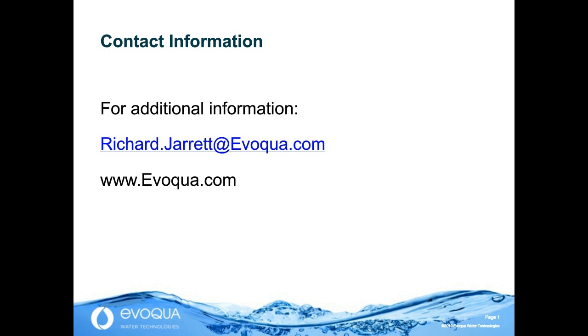Okay, thank you. Here's our next question. In the case where materials and filters are high temperature compatible, has superheated water sterilization been explored? Yes, and I would say to a small degree. There's so much data for microbial control at 80 degrees C, 90 degrees C, where having to do it under pressure is not required. Most systems operate in that realm.